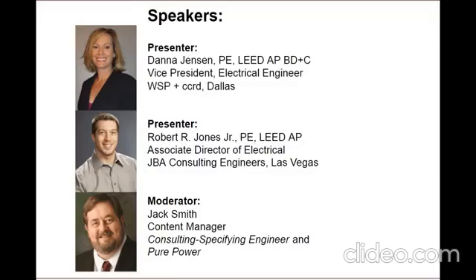But there are some other things that have changed. Those of you that are familiar with NFPA 99, in 2012 they completely revamped the whole thing and required a risk assessment for all hospitals. Well, in 2015 they changed it up a little bit. They said if you're going to design to a Level 1 system, then you don't have to do the risk assessment. And a Level 1 system is basically everything that we talked about here, having those three branches of power and everything else.